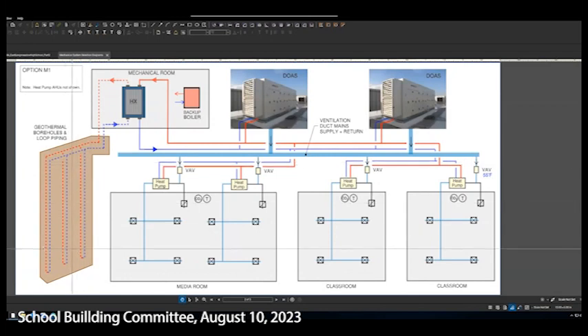In the geothermal option, we have a geothermal field here, which would occupy some acreage behind the school in the fields area. So these are essentially 500-foot deep boreholes that get drilled into the earth, and then a pair of tubes connected on the bottom with a little U-bend gets installed. You're pumping water in, and then the water is returning back out. It's a closed system. It's not like a drinking water well, an artesian well, where we're actually drawing water from the ground. In the estimate, we estimated about 130 of these boreholes, about 20 to 25 feet apart, so they would occupy a gridded area out in the field.